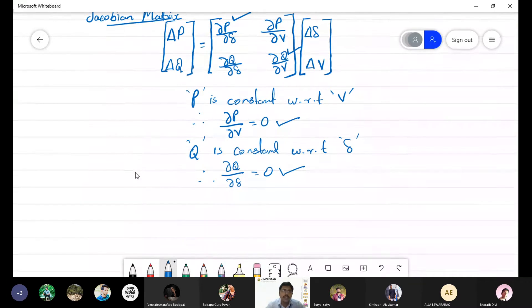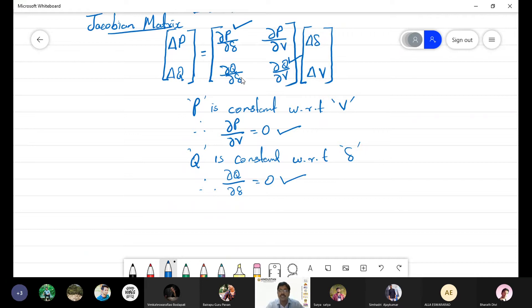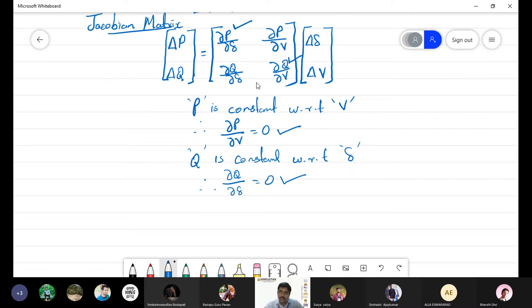The modified Jacobian matrix is what we call the decoupled form. Since in the coupled form we have all four terms — ∂P/∂δ, ∂P/∂V, ∂Q/∂δ, and ∂Q/∂V — but ∂P/∂V and ∂Q/∂δ are zero, there is no sense including them. In the decoupled Newton-Raphson method, we take out these two zero terms. Even if you include them, the value becomes zero or negligible. That's why we decoupled the Jacobian matrix.